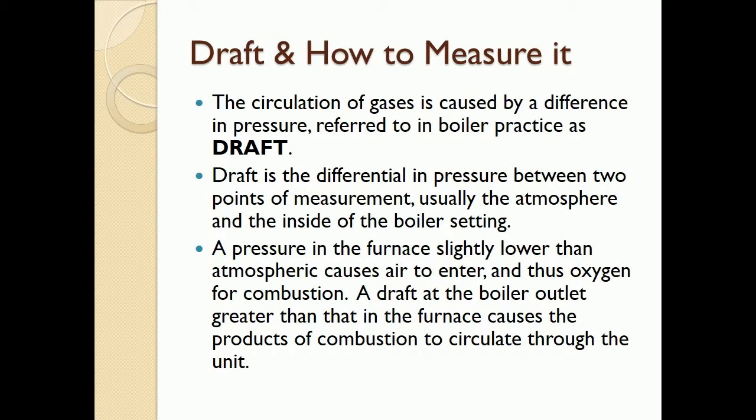Draft and how to measure it. The circulation of gases is caused by a difference in pressure, referred to in boiler practice as draft. Draft is the differential in pressure between 2 points of measurement, usually the atmosphere and the inside of the boiler setting.